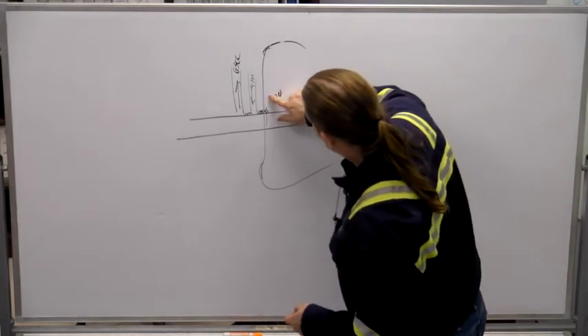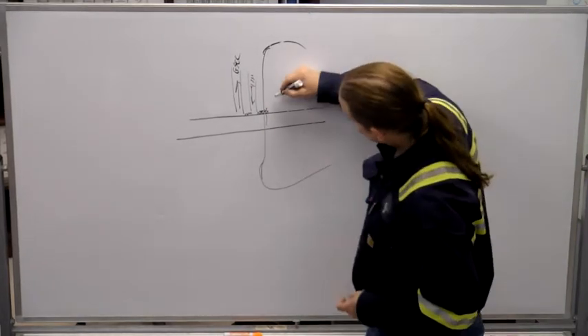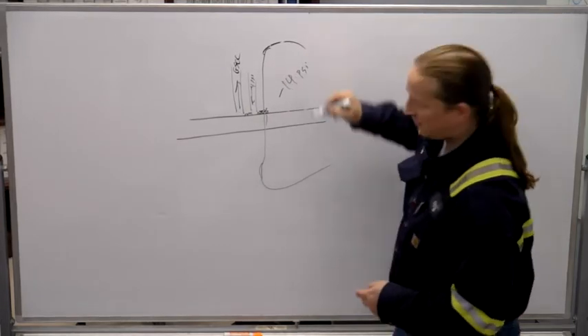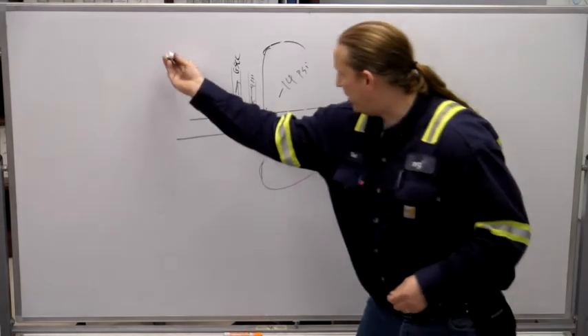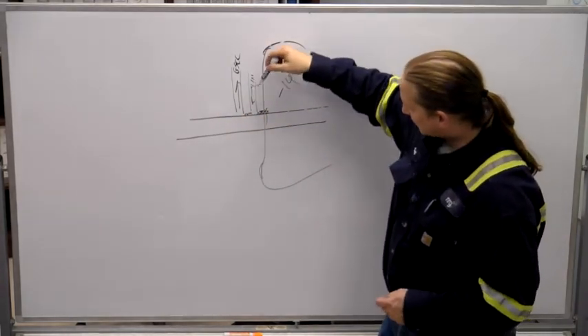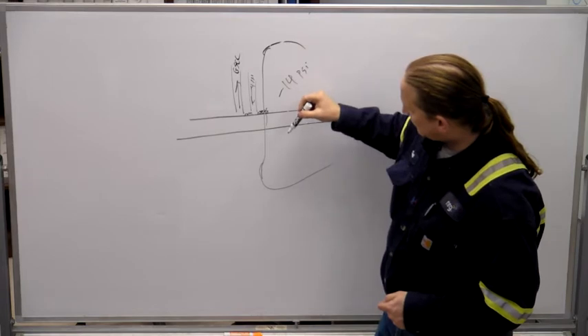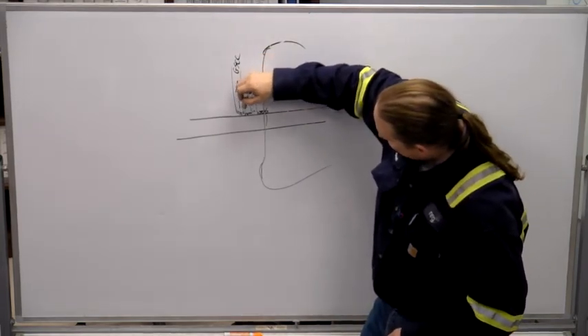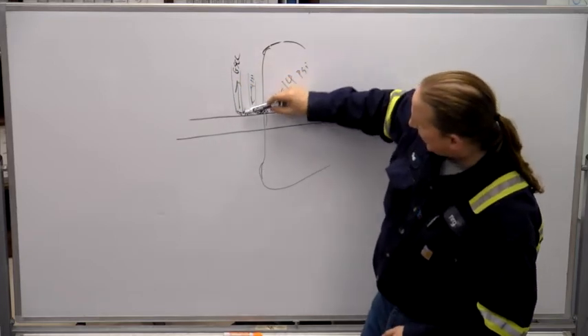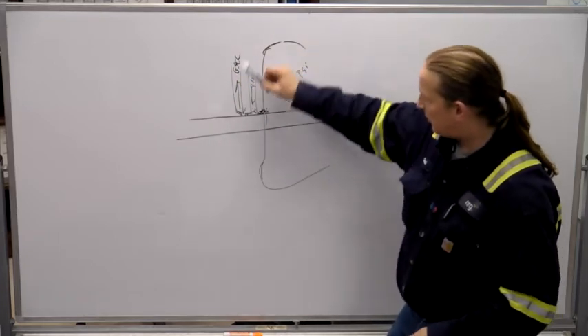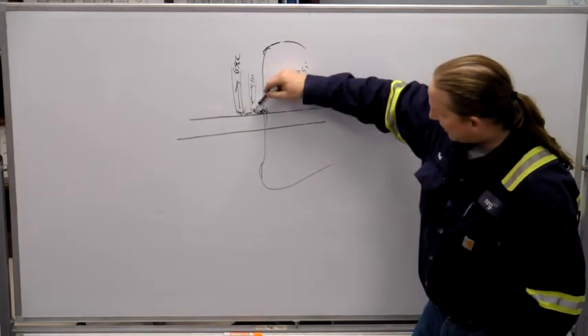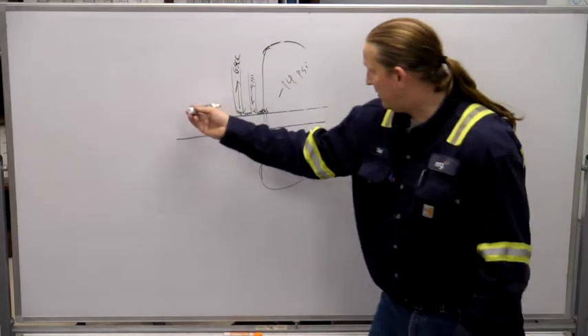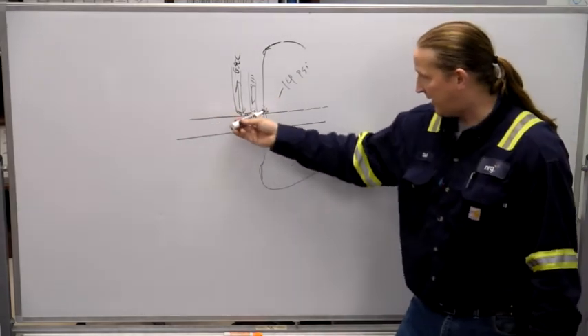If this side is under vacuum, minus 14 psi, then the air here is trying to get in. And you've got four pounds of steam being pushed there. And that steam is going to go that way, it's going to go that way. And the vacuum is going to catch it so that it doesn't fill up the space, but it's going to provide enough pressure to keep the air out. The air, without this four pounds of steam, would be trying to get in.